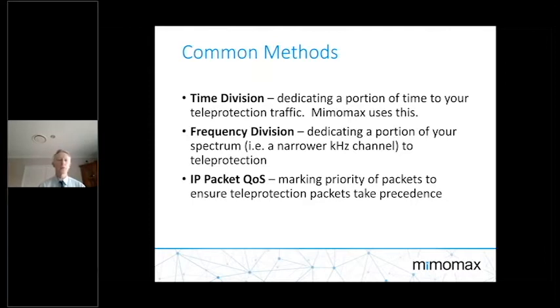The other option is frequency division, dedicating a portion of your spectrum, i.e. a narrower channel, to teleprotection. And then there is IP packet quality of service marking, marking priority packets to ensure teleprotection takes precedence. Mimomax don't use this - we often find that some of those QoS rules, or how that's been set up, don't provide the most reliable outcome. So we've landed on time division, and I'll talk to that in a little more detail in the coming slide.